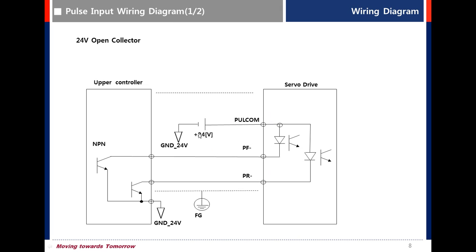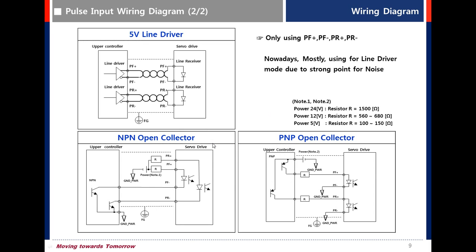PULCOM connects to 24V. This is 5V line drive. For NPN open collector wiring and PNP open collector wiring using 24V open collector, you don't need a resistor — just connect CN1 pin 49 to plus 24V. But if using 12V or 5V, you need to use a resistor. Refer to note 1 and note 2.